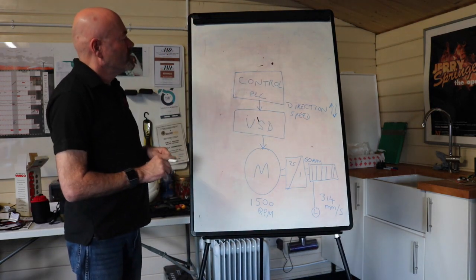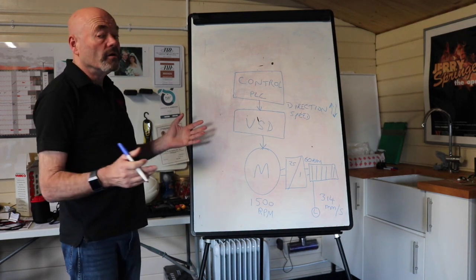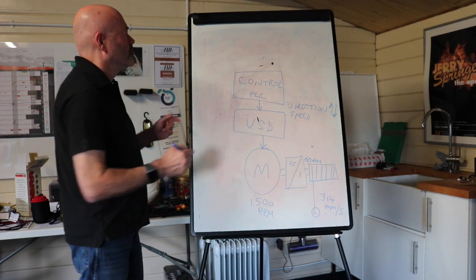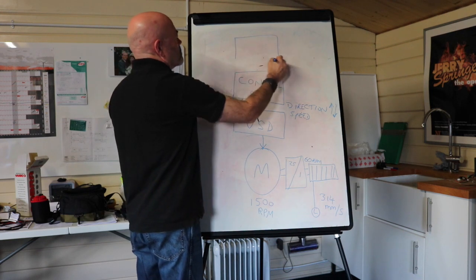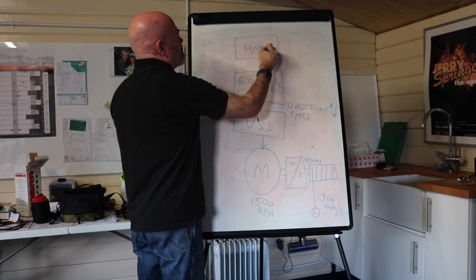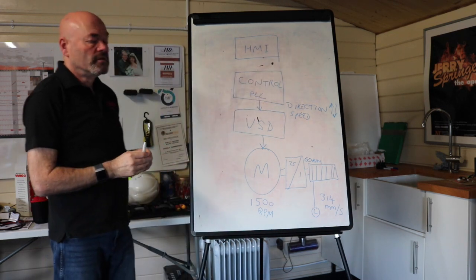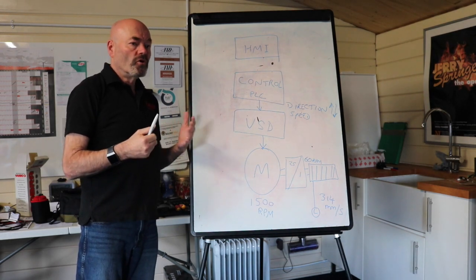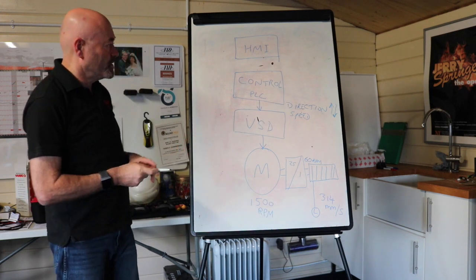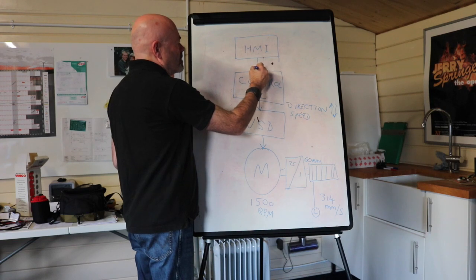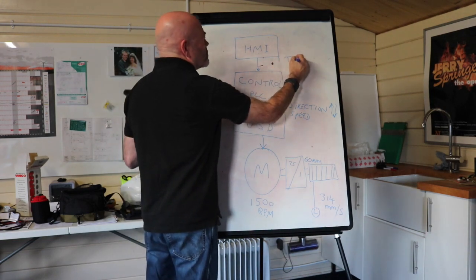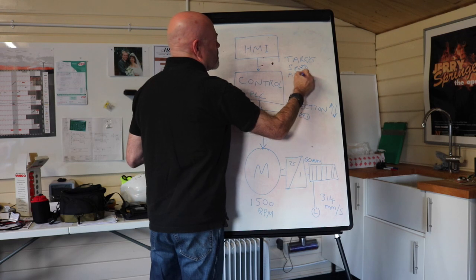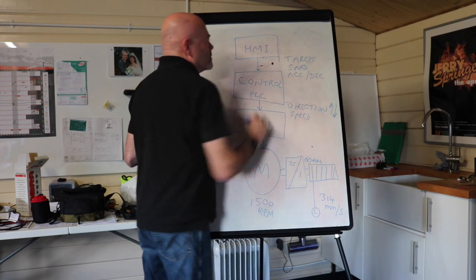Now the control system needs to be told by the operator where to go, what position do we want to go to, how fast do we want to travel at, how much acceleration, deceleration do we want to do. So for that we have an HMI, human machine interface. Now this could be a computer, laptop, a touch screen or a console which generally has a computer inside it. And this gives information in form of target, speed, accel, decel as a minimum.